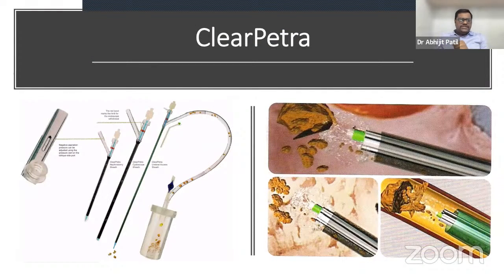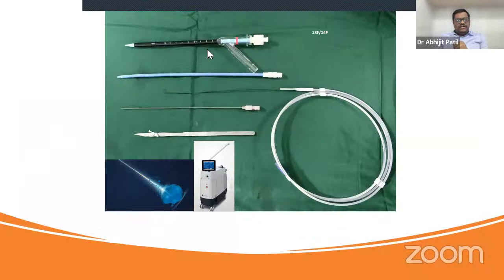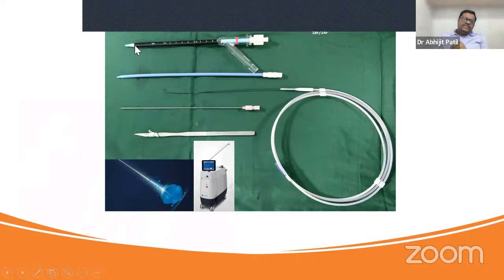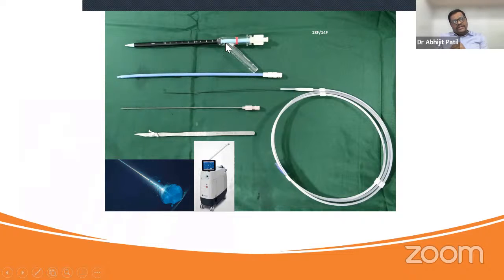Coming on to the first sheath, which is the ClearPetra sheath, this is the setup which is required: the initial puncture needle, then you require a glide wire, the fascial dilator, and this is the ClearPetra sheath. This is an 18 French sheath made up of plastic or PTFE, and it has an oblique offset and a red mark, so that you come till that red mark, then the fragments will be sucked up through the offset. It has a marking that helps you understand till what depth you have gone inside, and it has its own dilator.